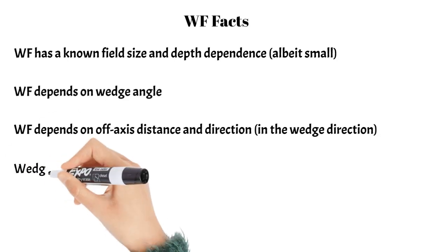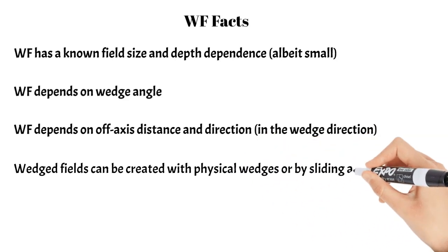Wedge fields can be created with physical wedges or by sliding a jaw across the field. Physical wedges are placed in the beam and completely change the photon spectrum and the shape of the dose distribution in the phantom or patient. You can also create the same effect by sliding a jaw across the field, which is more advantageous because it's not a completely different spectrum beam.